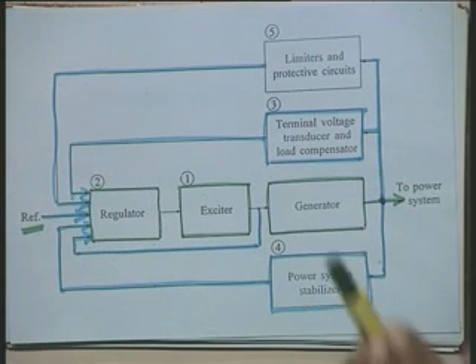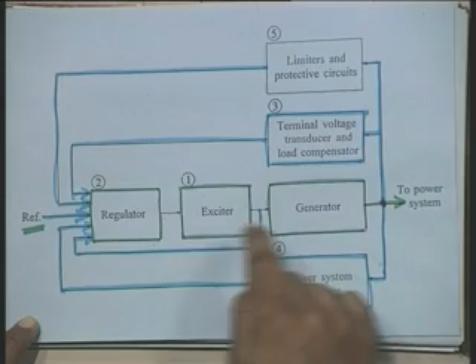And this block diagram is just to give you the basic features of the excitation system, but it senses not only the generator parameters, but exciter parameters also. The exciter should also not go beyond its operating limits. Limiters just look, and the moment limits are crossed, they take action. The action may even be to trip the synchronous generator from the system. Suppose it feels the synchronous generator is going outside the capability limit, then these limiters can even trip the generator. Very complex control and protective functions are provided, and our main consideration is that we take the best out of the synchronous generator from the system point of view, and at the same time its safety is ensured.